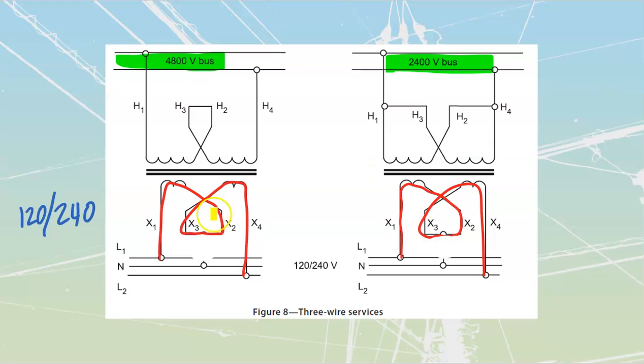All right, let's go back to what we're doing down here. Once we create the 240 volt connection inside here, the next thing that needs to happen is we need to center tap that. Center tapping is the term we use for when we take our transformers and tie into the very center portion of them. What I have now is a tap going to this common piece, the X2, X3, tied together, and then a tap going down to this line, which we'll term our neutral.